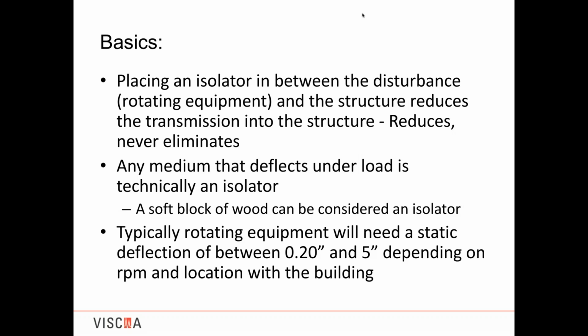Now, an isolator, effectively any medium that deflects under load is technically an isolator. All we need is a little bit of deflection of some medium that goes between, and as I said, in the slide you can see even a soft block of wood. As long as the wood deflects and can maintain its deflection and support the equipment, it'll do something. It won't do much. You won't get much efficiency out of it, but it will technically be considered an isolator.